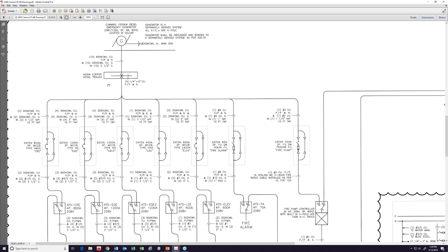However, these conductors are protected in the sense that they have to be sized no less than 10% of the generator size, at a 10-foot tap. And that is why in the 2014 NEC and the newer versions, they added this requirement. So you have a very short wire that will be deemed protected because it is very short, only 10 feet, and 10% of the size of the generator.